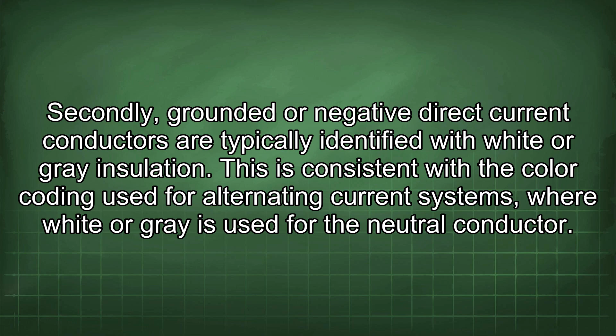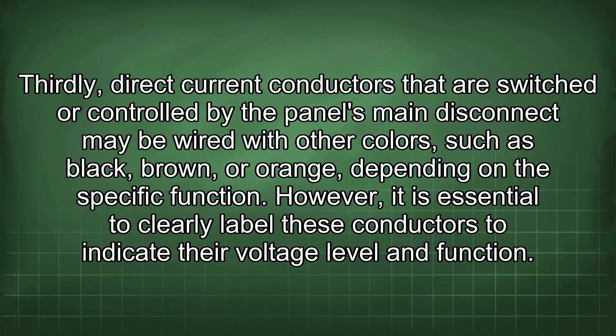Thirdly, direct current conductors that are switched or controlled by the panel's main disconnect may be wired with other colors, such as black, brown, or orange, depending on the specific function. However, it is essential to clearly label these conductors to indicate their voltage level and function. To summarize, the key takeaway is that red is the designated color for direct current conductors that remain energized when the panel is off, regardless of the source of the power.